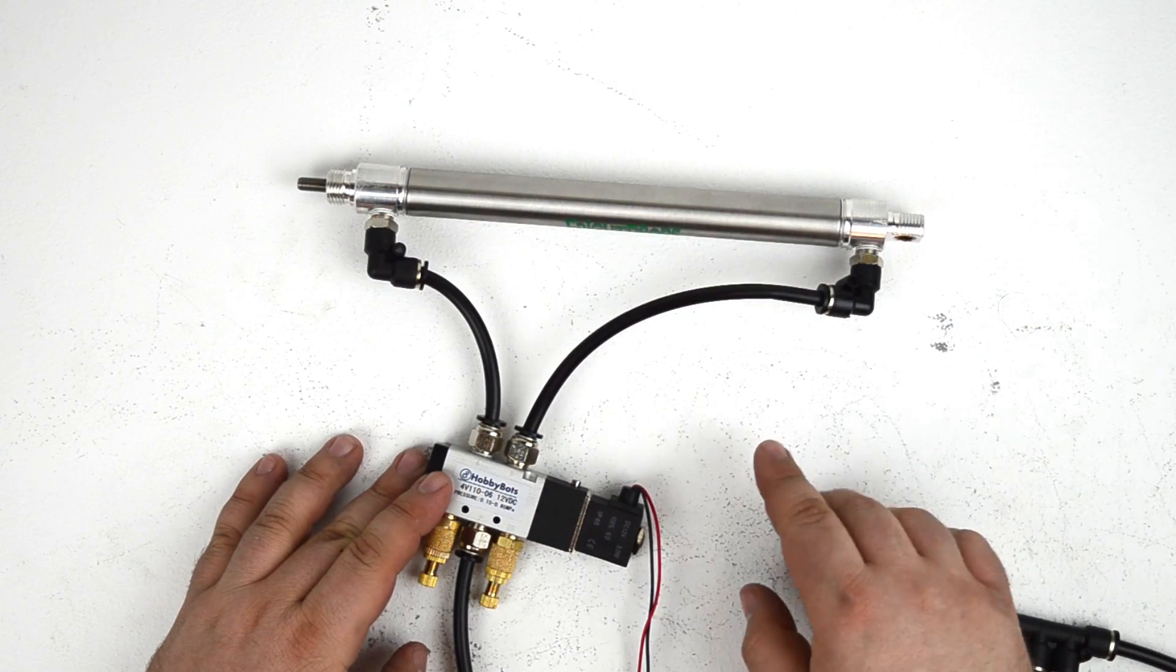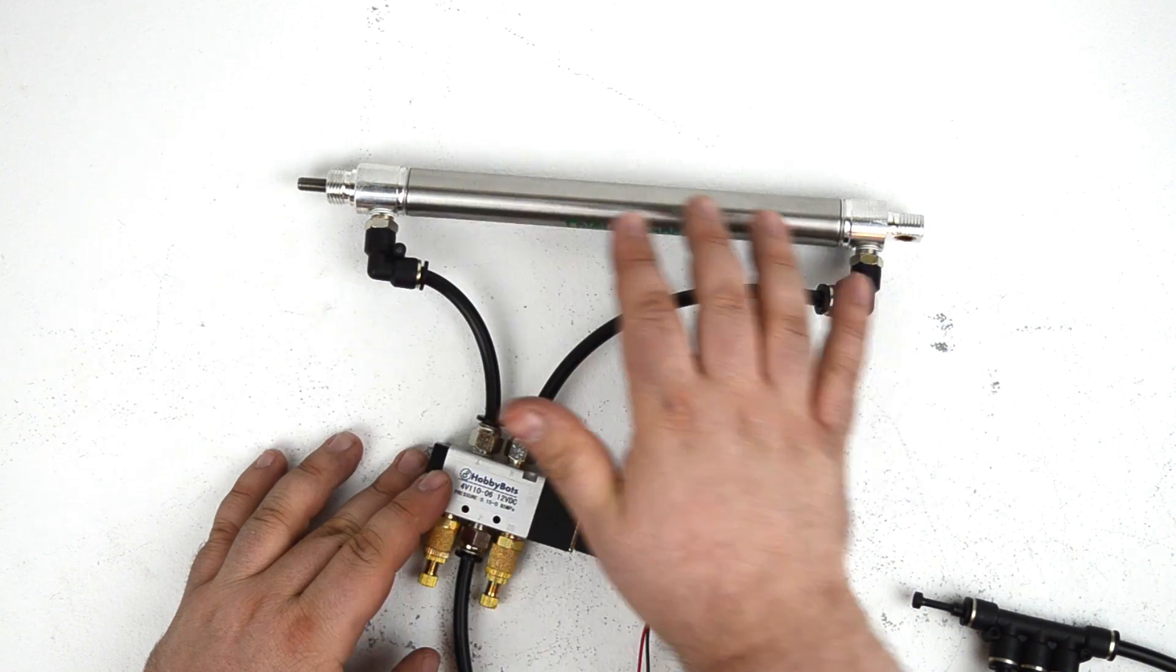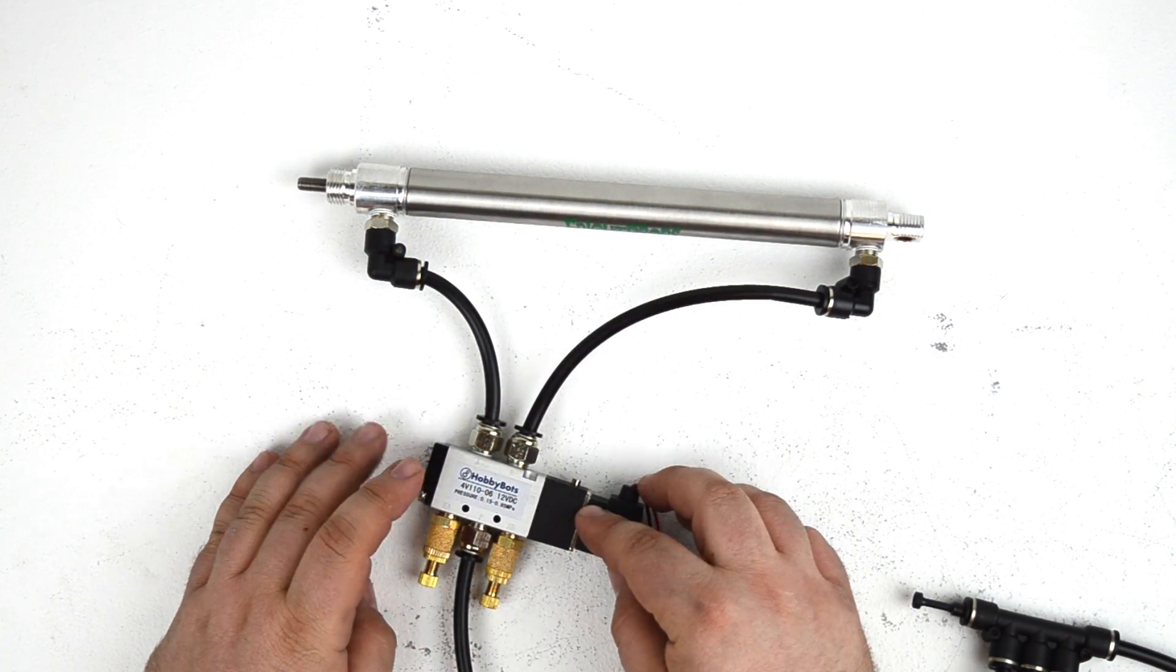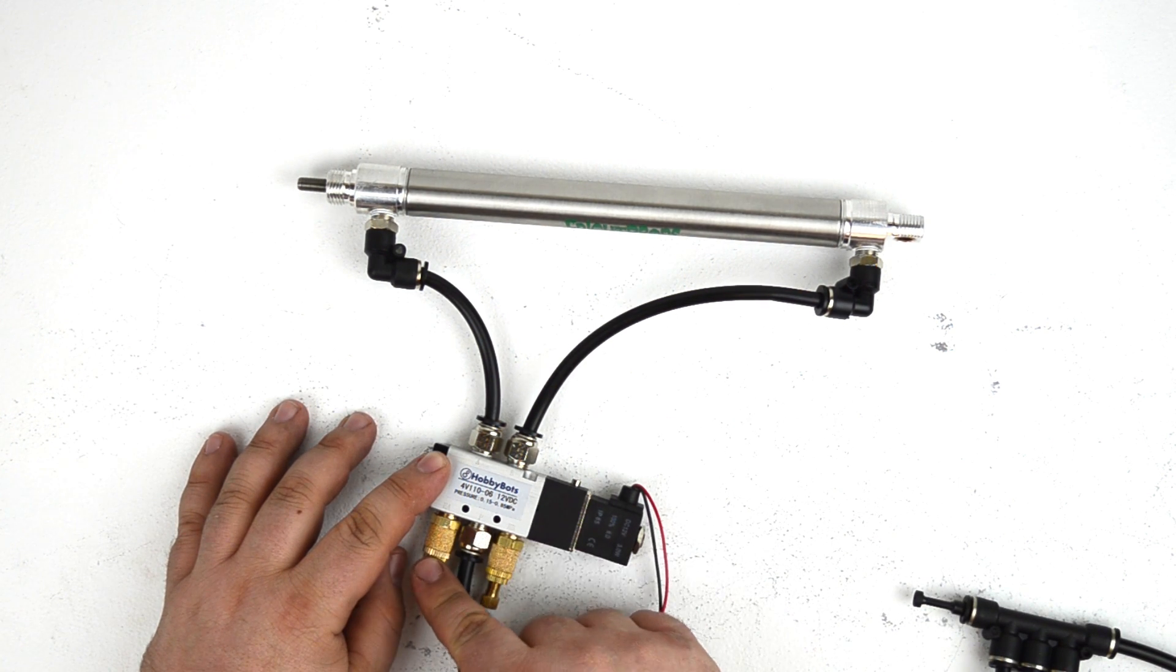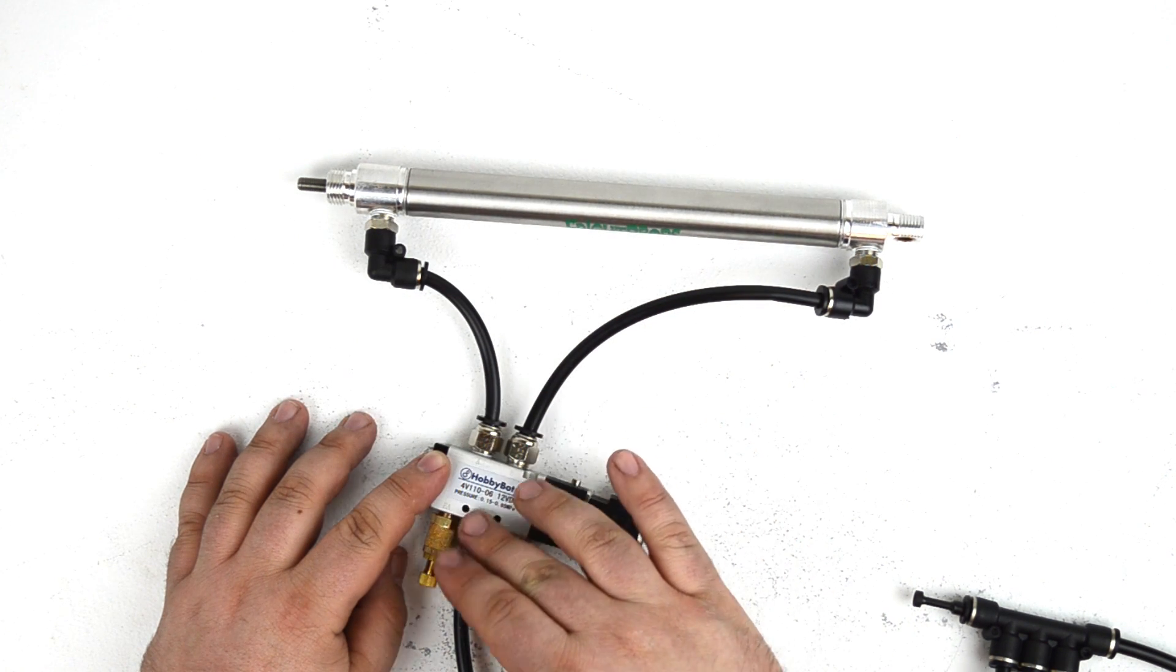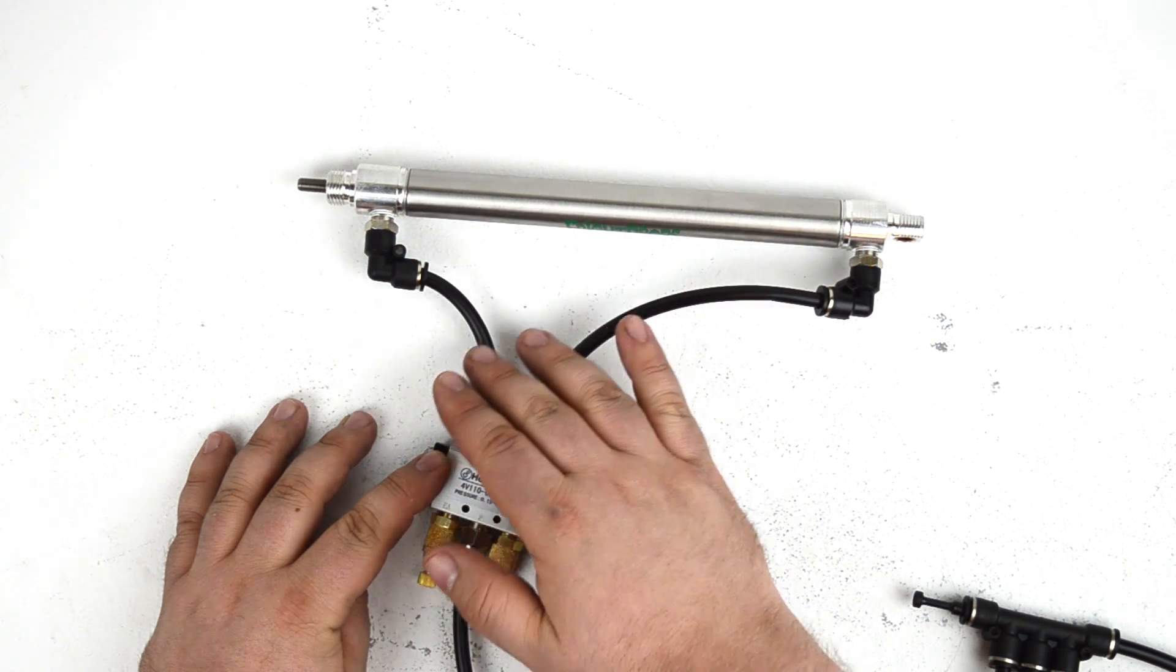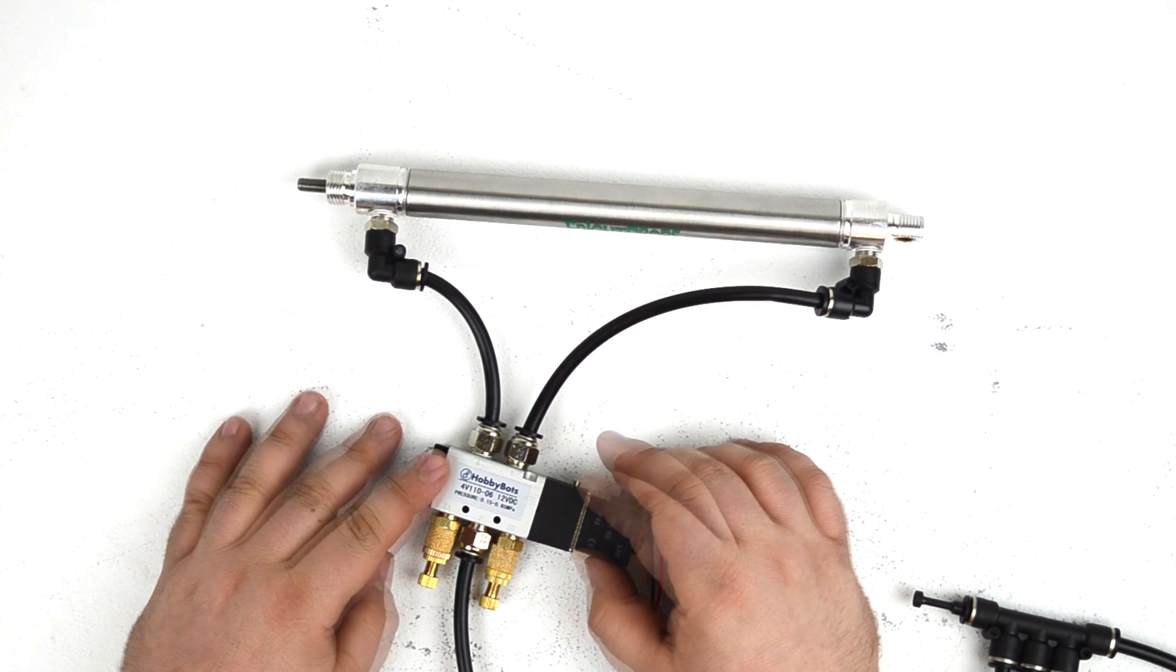Another way to control the speed of a cylinder is that rather than adjusting the flow of air at the cylinder ports themselves with flow control fittings here, you can control the flow of air at the solenoid exhaust ports here. This works by restricting the flow of air as it passes back from the cylinder out the exhaust of the solenoid. You can meter it here rather than metering it as it comes into the solenoid. They both accomplish the same effect, just in different places.